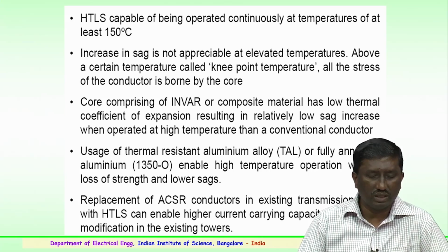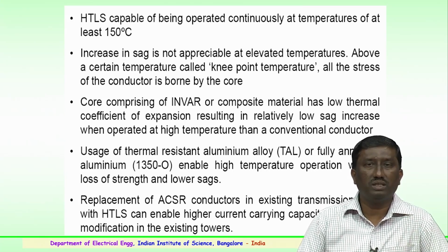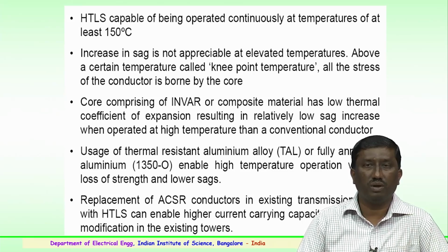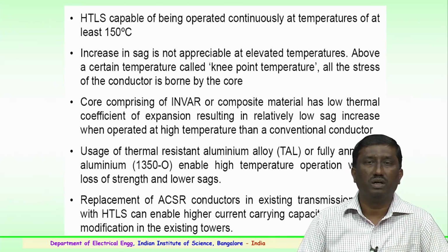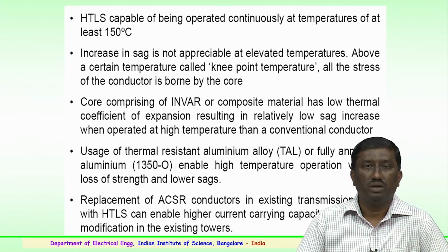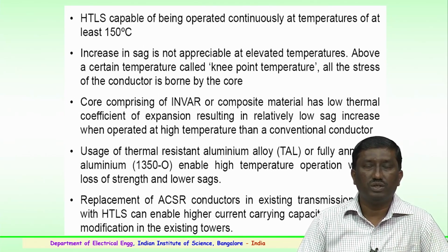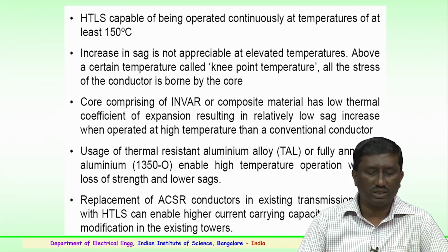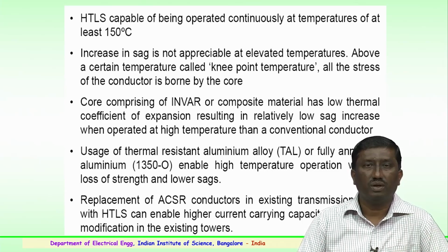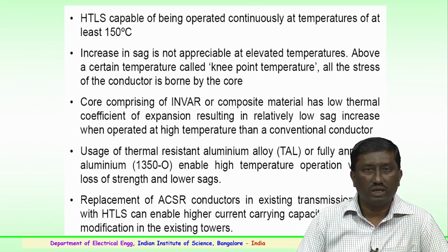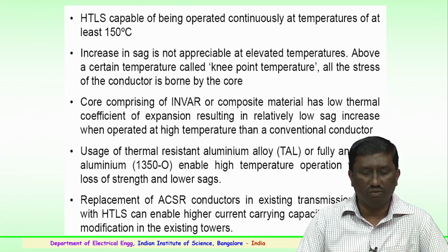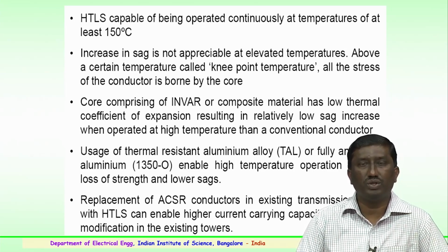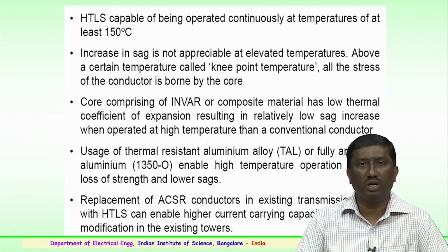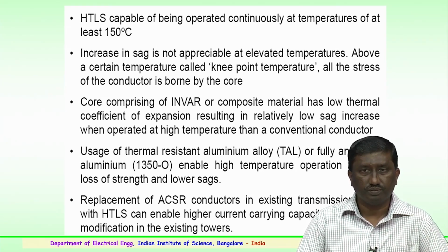In these conductors, the increase in sag is not appreciable at very high elevated temperatures between 150 to 200 degrees. Above a certain temperature, which is known as the knee point temperature, all the stress of the conductor will be borne by the core, that is the characteristic of the conductor. The core of the conductor, basically comprising invar or a composite material, has a low thermal coefficient of expansion.